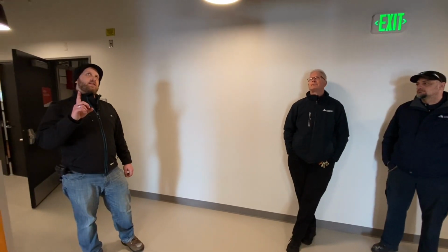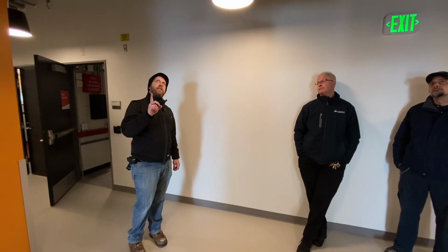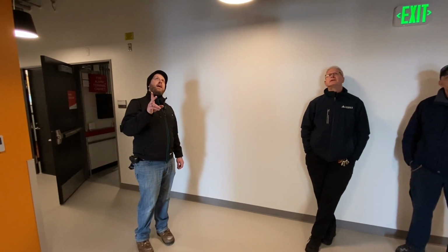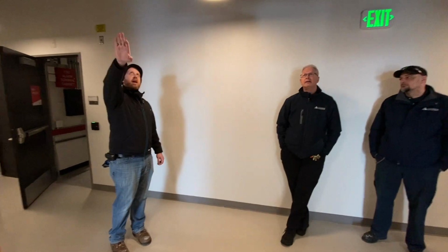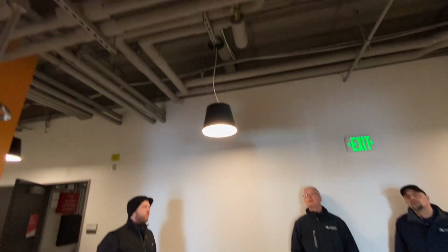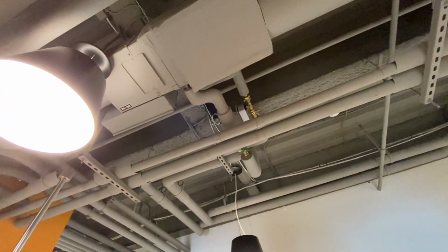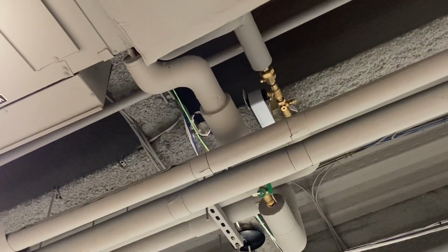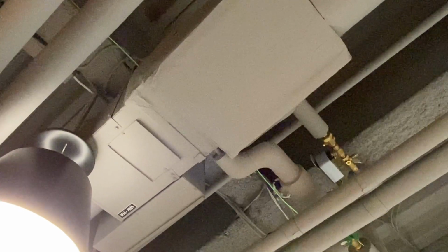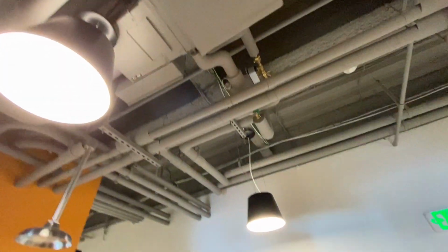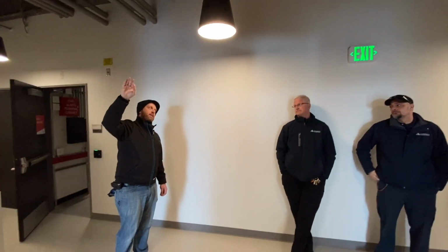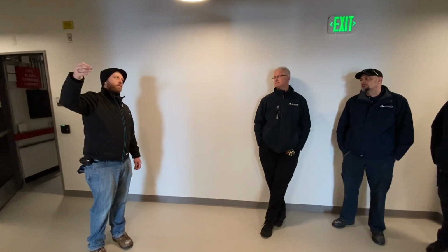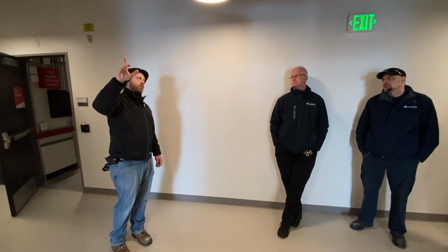Yeah, so I think this is not really doing a lot of air. Don't quote me on this, it's small, so it's probably 100. Yeah, and we have a reheat here too. Right, I see the reheat coming off the building system. So that's providing neutral air. Yeah, it's all neutral air. I think it resets, I forget the sequence off the top of my head, I apologize, but it resets based on outside air. So as it gets colder, we're going to provide 60, so these reheat coils aren't working as hard.